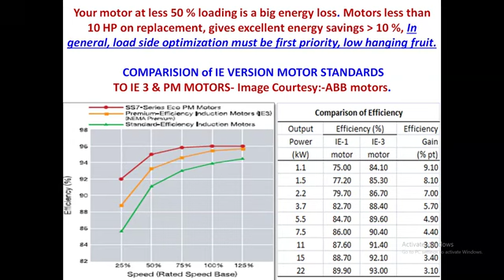The Bureau of Energy Efficiency has given a lot of inputs, especially they have clarified only four steps. Wherever possible for a given industry, as I said before, instead of giving 240 volts to your LED tube light, you just give 200 volts. Instead of giving 415 or 440 volts to a motor which is only three-quarters loaded, you just operate it at 400 volts. Trimming the input side is a low cost, zero cost exercise, and it is possible. Accurate monitoring is the first step, monitoring the power, kilowatt and kVA, for a given equipment, and then the trimming of the energy inputs.